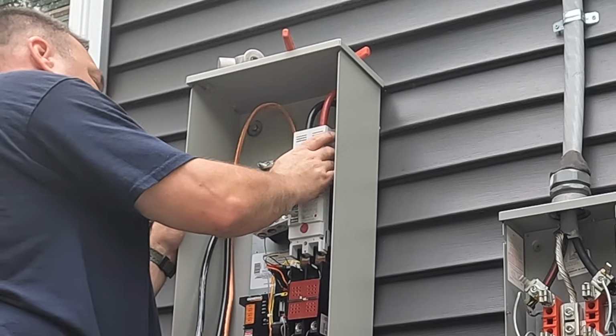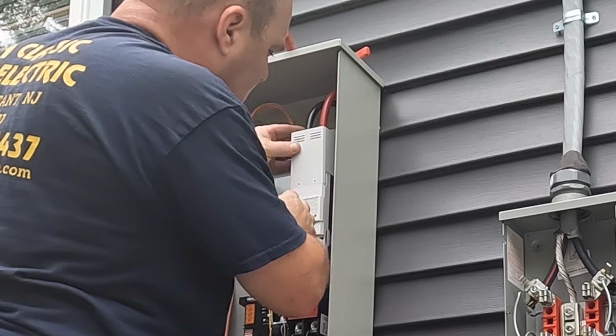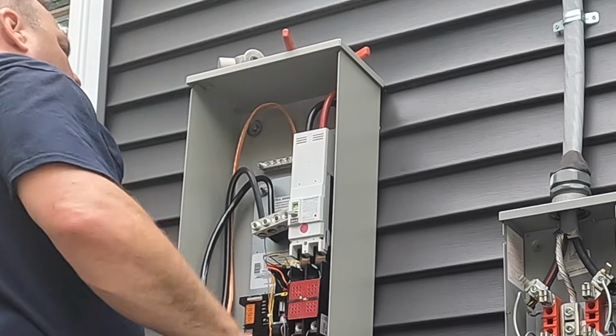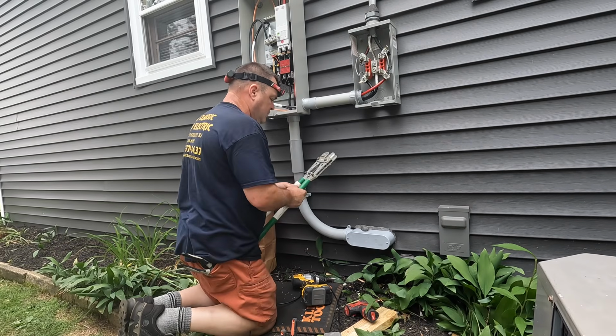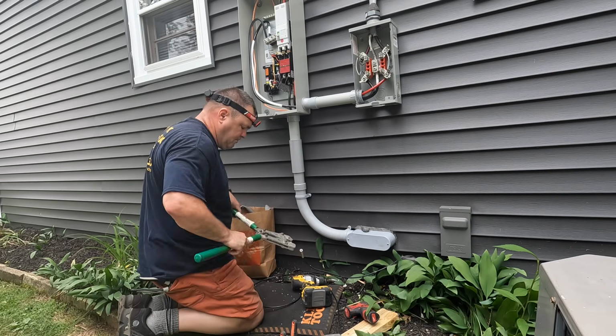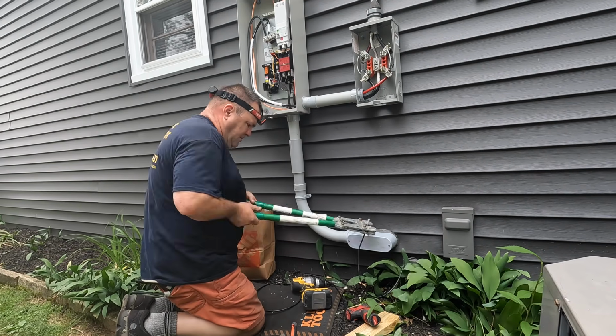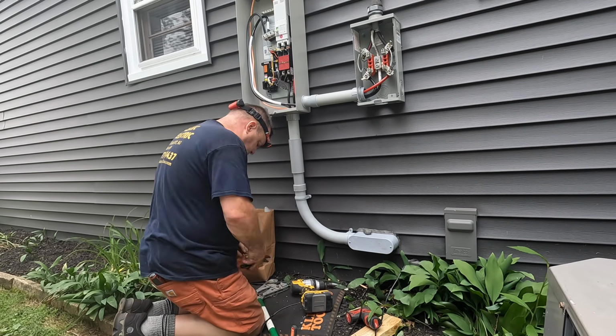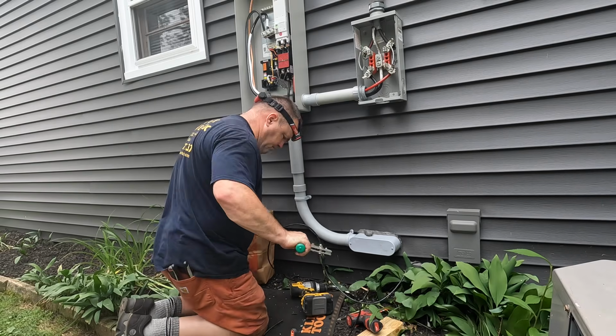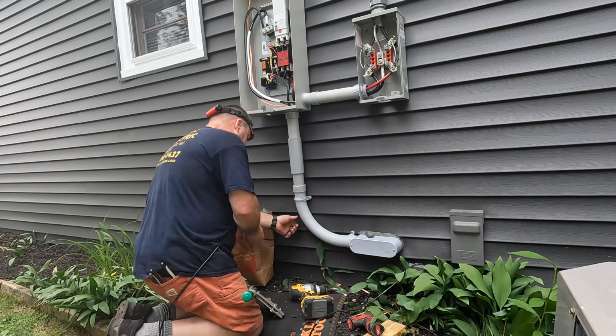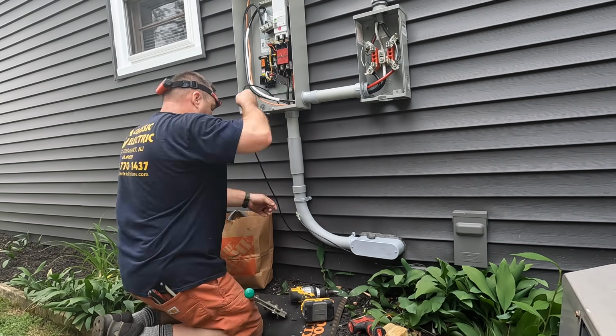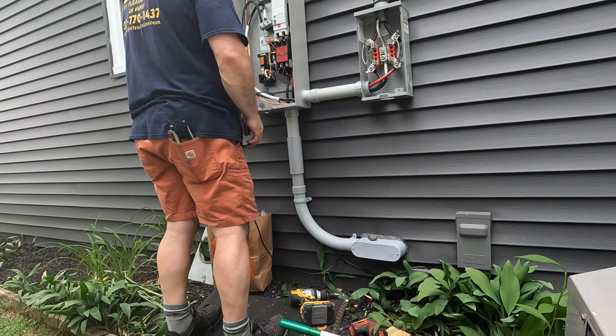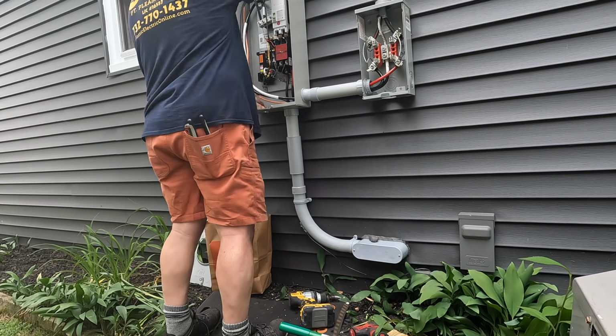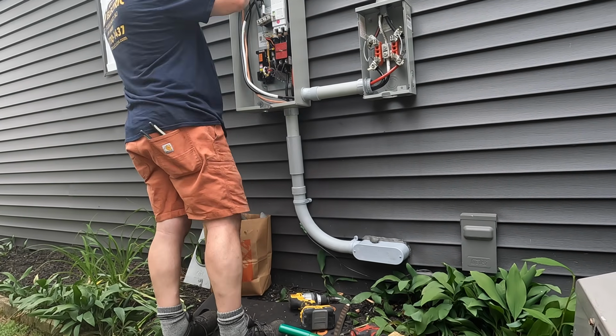One of the things I also have to do is extend both of my grounding electrode conductors, and in this case there were 3. There were two individual conductors going to each of the ground rods, and then of course the water main, which is the number 2 aluminum. They both had to be extended, and that's what I'm doing here. I am crimping and extending one of my ground rod electrical conductors so it's long enough to go into the main disconnect here at the transfer switch.